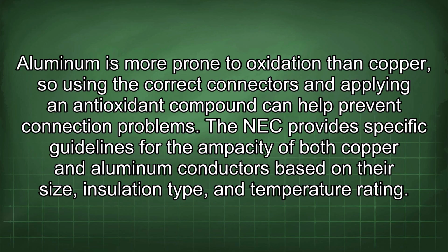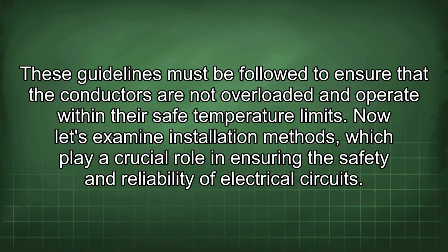Aluminum is more prone to oxidation than copper, so using the correct connectors and applying an antioxidant compound can help prevent connection problems. The NEC provides specific guidelines for the ampacity of both copper and aluminum conductors based on their size, insulation type, and temperature rating. These guidelines must be followed to ensure that the conductors are not overloaded and operate within their safe temperature limits.